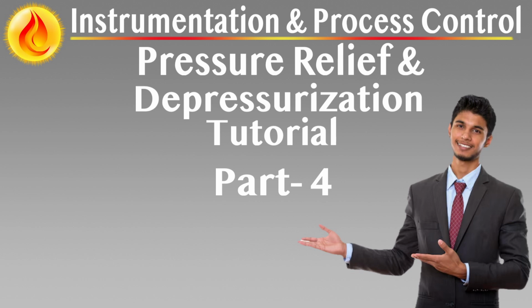Accounting for multiple units and common failures. In integrated facilities with multiple units connected to a shared flare system, for a site-wide utility failure, use 100% of the relief load from one unit, the most critical, plus 50% of the relief loads from each of the other units. This approach assumes process dynamics and protective controls will stagger the response.